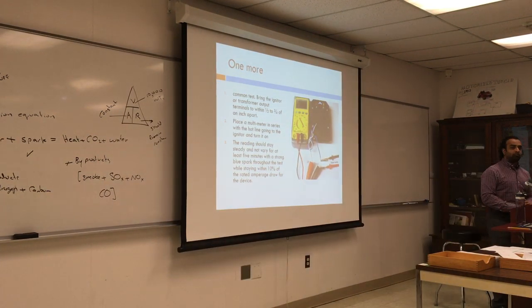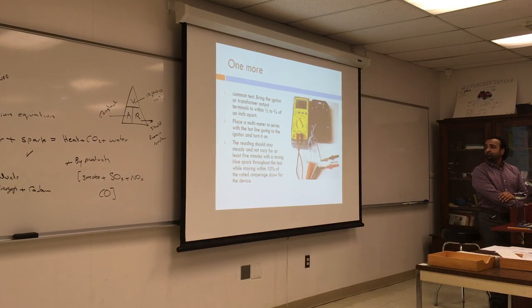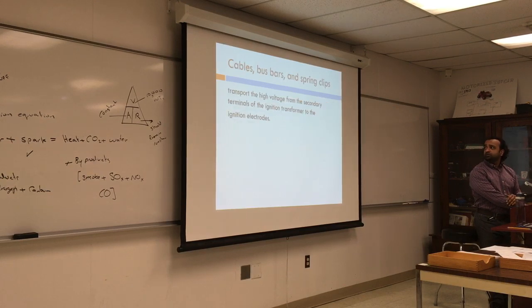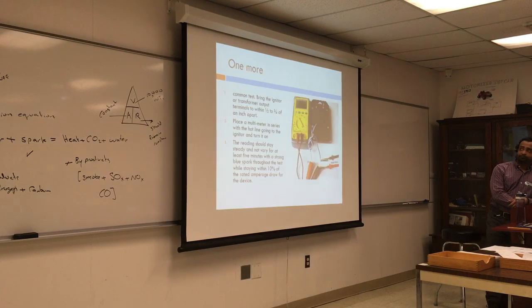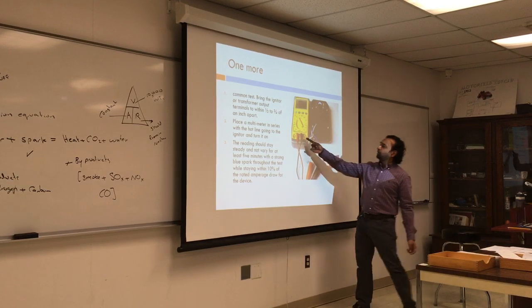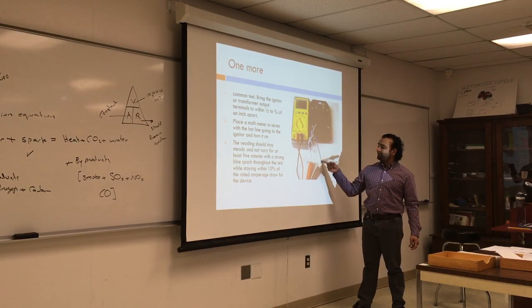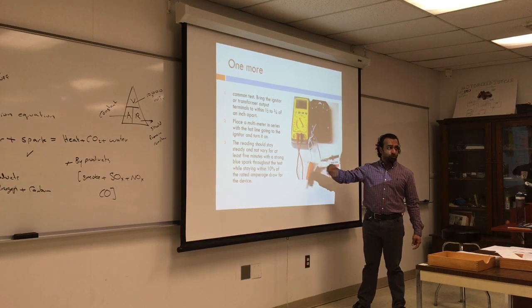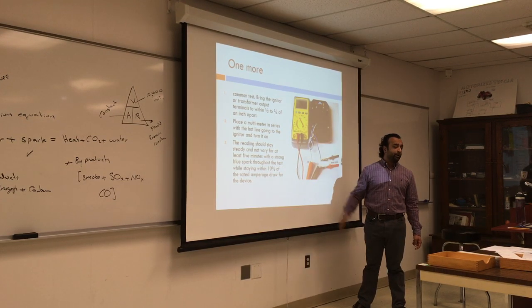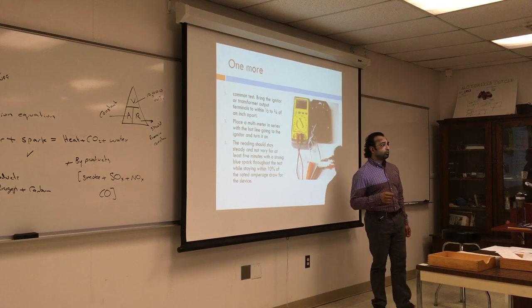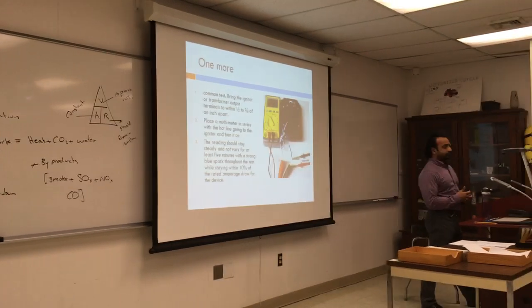So you're measuring amperage in this test? Yeah. You measure the amperage and you wait for the change. It stays the way it is, or within 10%. So that's actually working through the meter now. The meter is completing the circuit so you can read the amperage. This meter is not a clip-on, it's connected in series. But if you have a clip-on meter, just clip it on one of the wires or coil it twice, and wait for the reading, and keep watching it for 5 to 10 minutes.